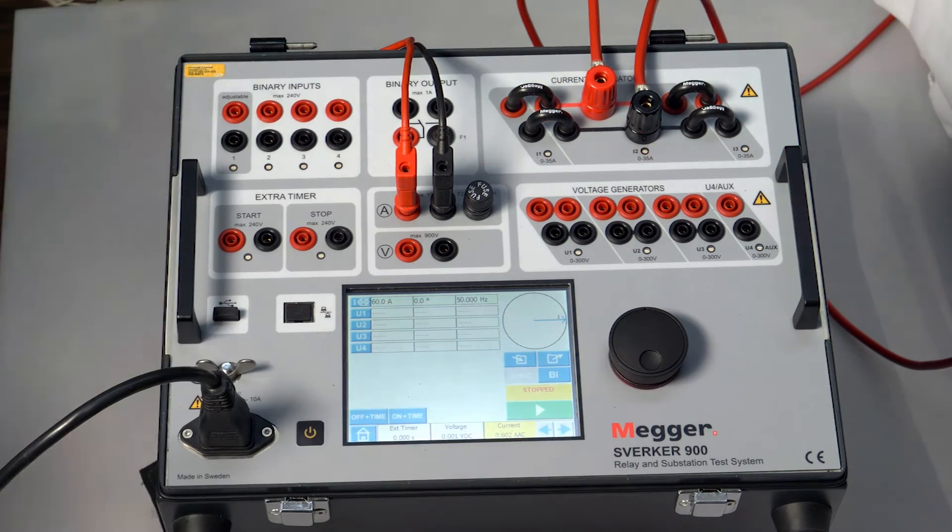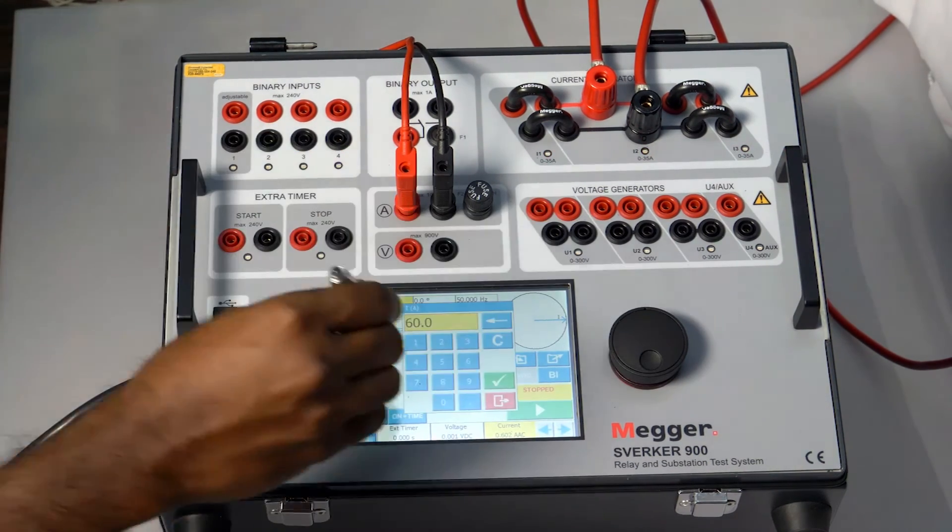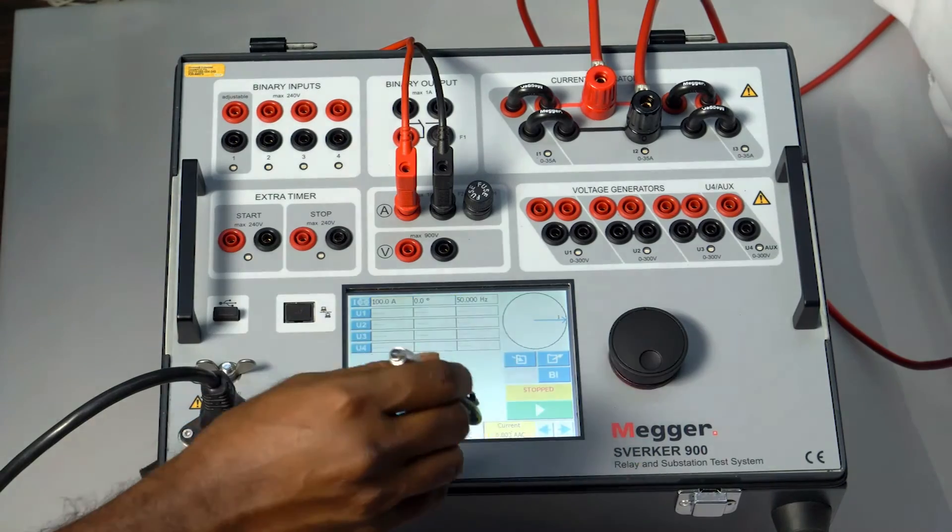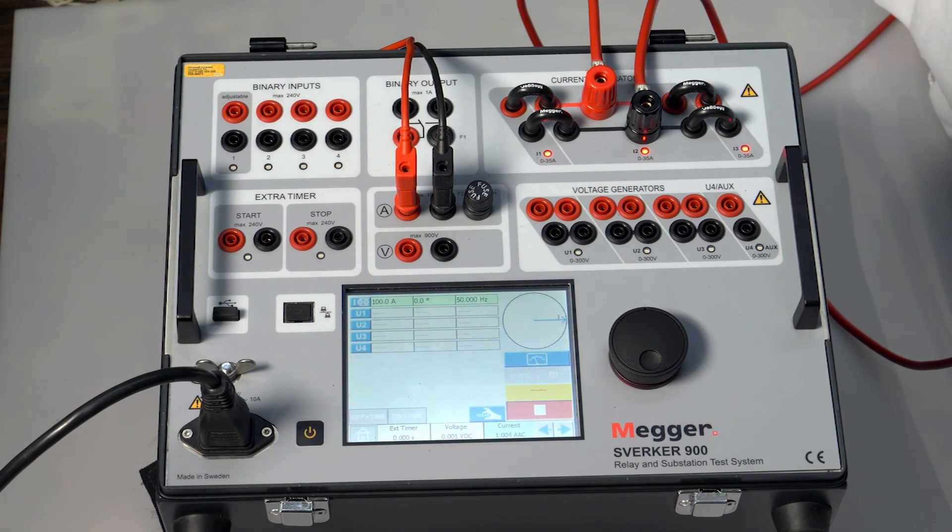80 amps, 0.8 is calculated. 0.803 is the measured one. And the full load current 100 amps, 1 amp is calculated value. And the measured is 1.005.